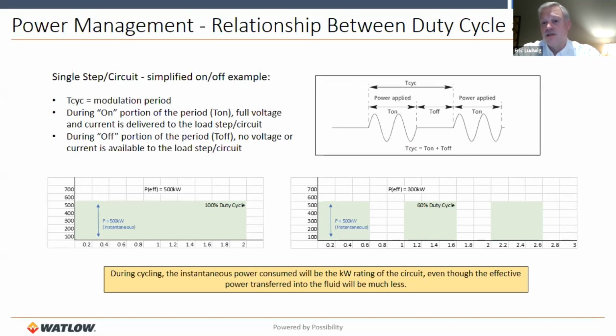And that, because of an electric heating element, is the actual power that will be placed into the heating system itself. The heating system will see that 300 kilowatts. However, the instantaneous power when that's on is 500 kilowatts, and that becomes important. You have to understand and analyze your feeder system to understand whether it can withstand that instantaneous power load. So let me give a quick example of that.